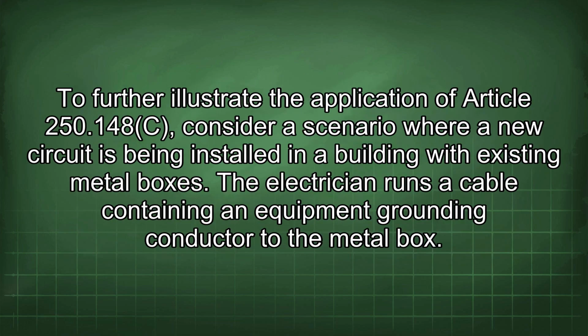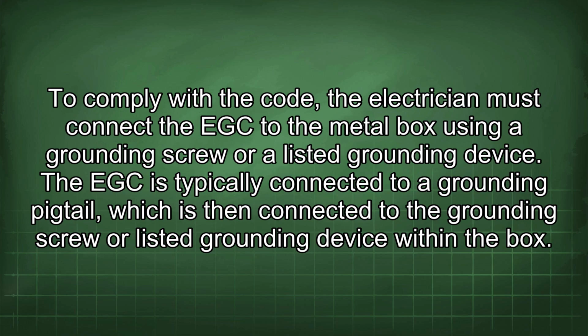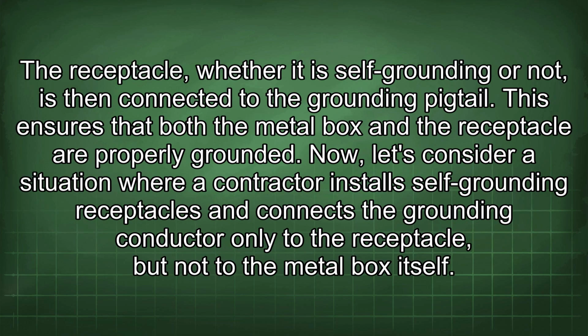To further illustrate the application of Article 250.148C, consider a scenario where a new circuit is being installed in a building with existing metal boxes. The electrician runs a cable containing an equipment grounding conductor to the metal box. To comply with the code, the electrician must connect the EGC to the metal box using a grounding screw or a listed grounding device. The EGC is typically connected to a grounding pigtail, which is then connected to the grounding screw or listed grounding device within the box. The receptacle, whether it is self-grounding or not, is then connected to the grounding pigtail. This ensures that both the metal box and the receptacle are properly grounded.